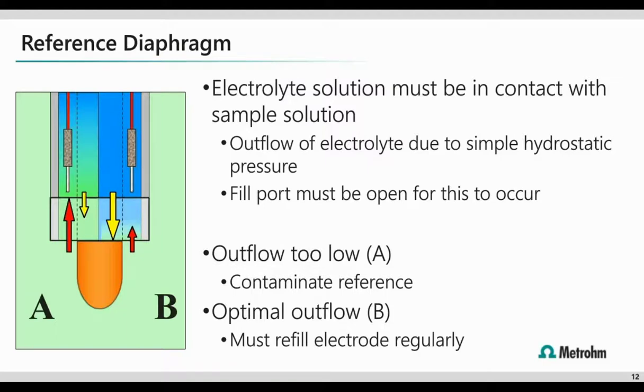So if we focus on side A, here, this is what happens when we let the electrolyte level drain to very low levels. When we put that electrode into the sample solution, the pressure on the outside of the electrode is greater than the pressure on the inside. So what happens is we have the sample creep, follow that red arrow, creep up into the inside of the electrode. And then what happens is we are contaminating the reference chamber and ruining the electrode beyond repair here. Looking at side B, simply keeping the electrolyte solution topped off allows the solution to be flowing in the right direction. So that yellow arrow, we want that one to be bigger. We want the electrolyte to be flowing out. So really the take home here is keeping the electrolyte filled up properly is key to not only a properly working electrode, but also preventing damage.